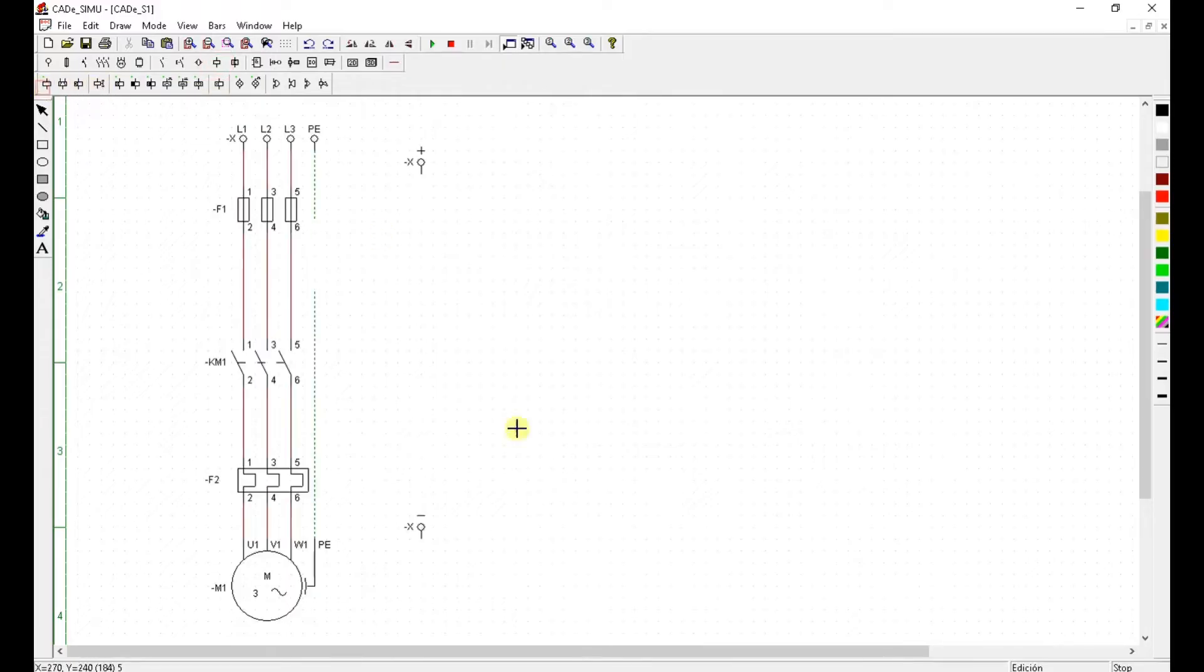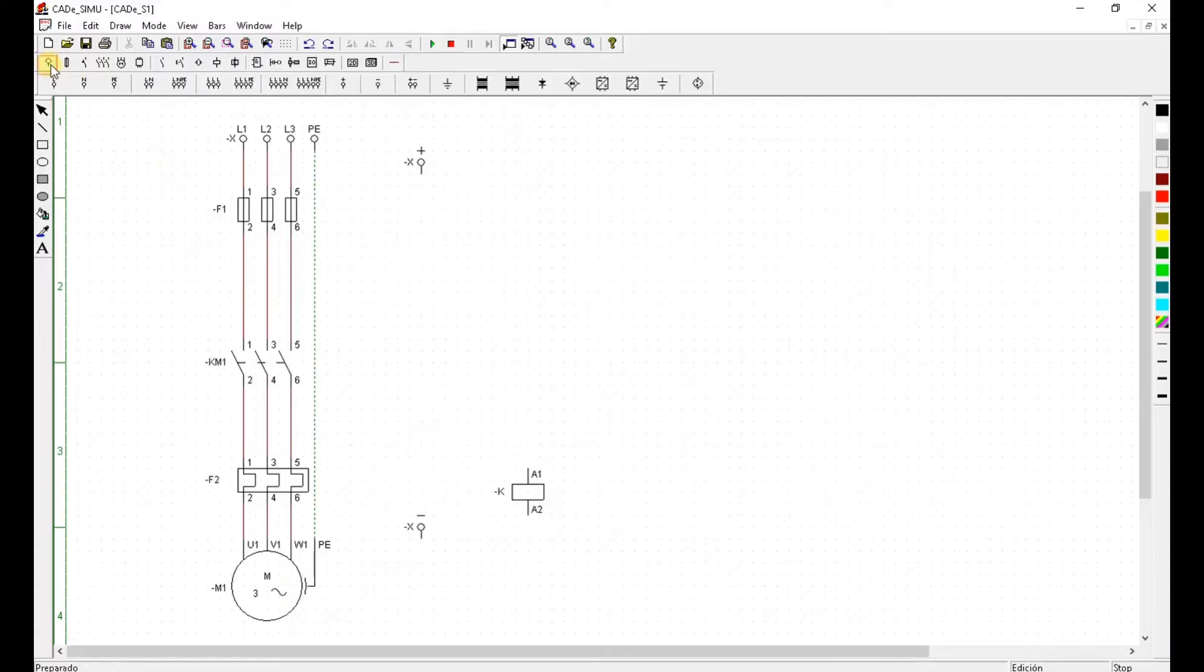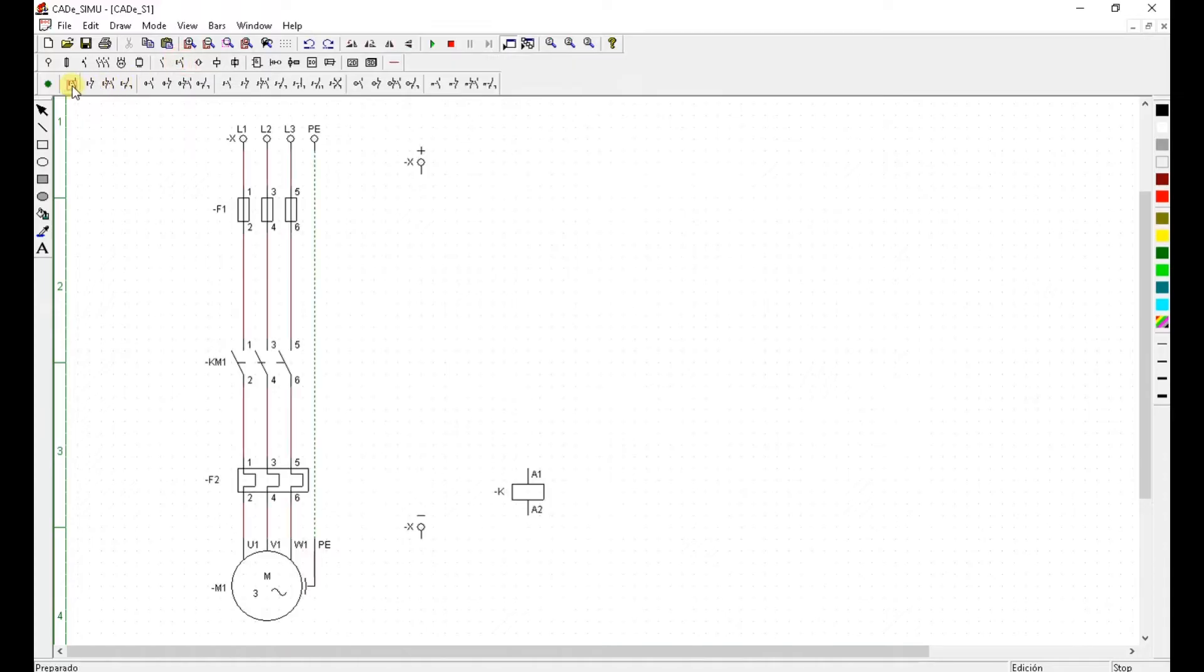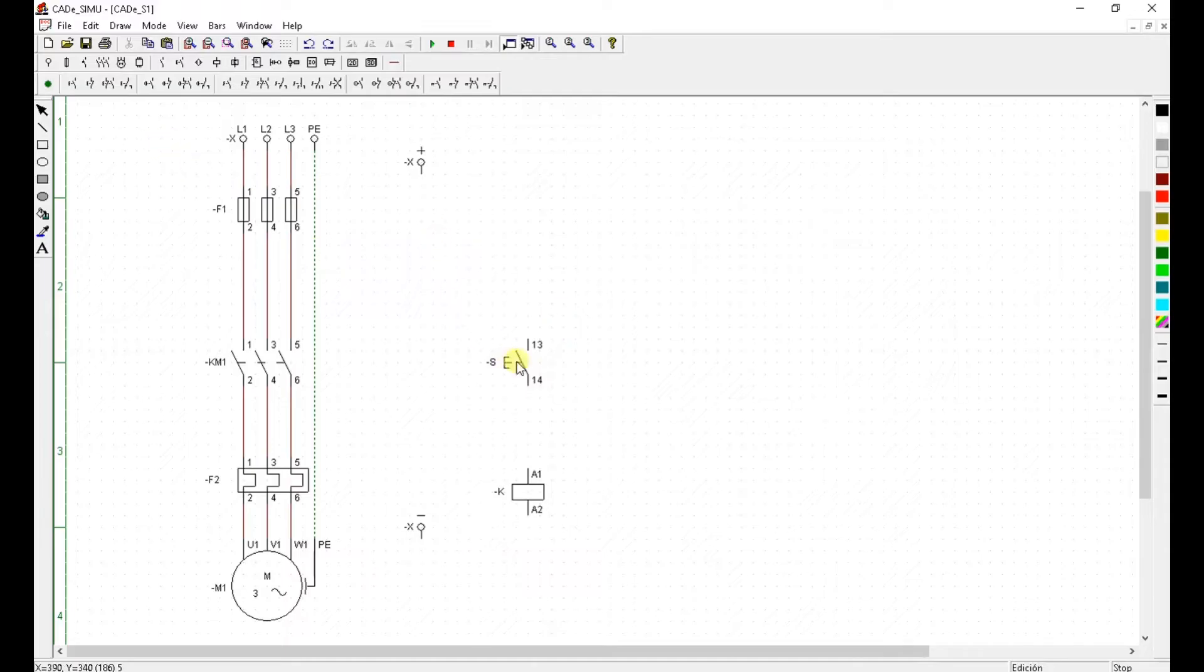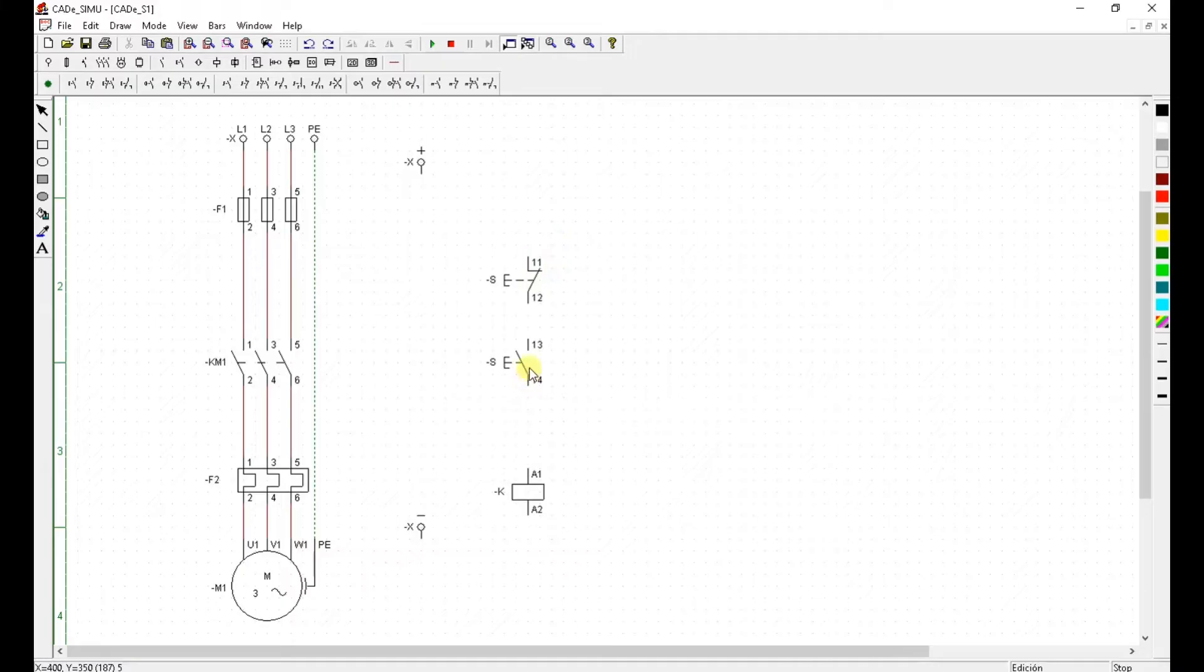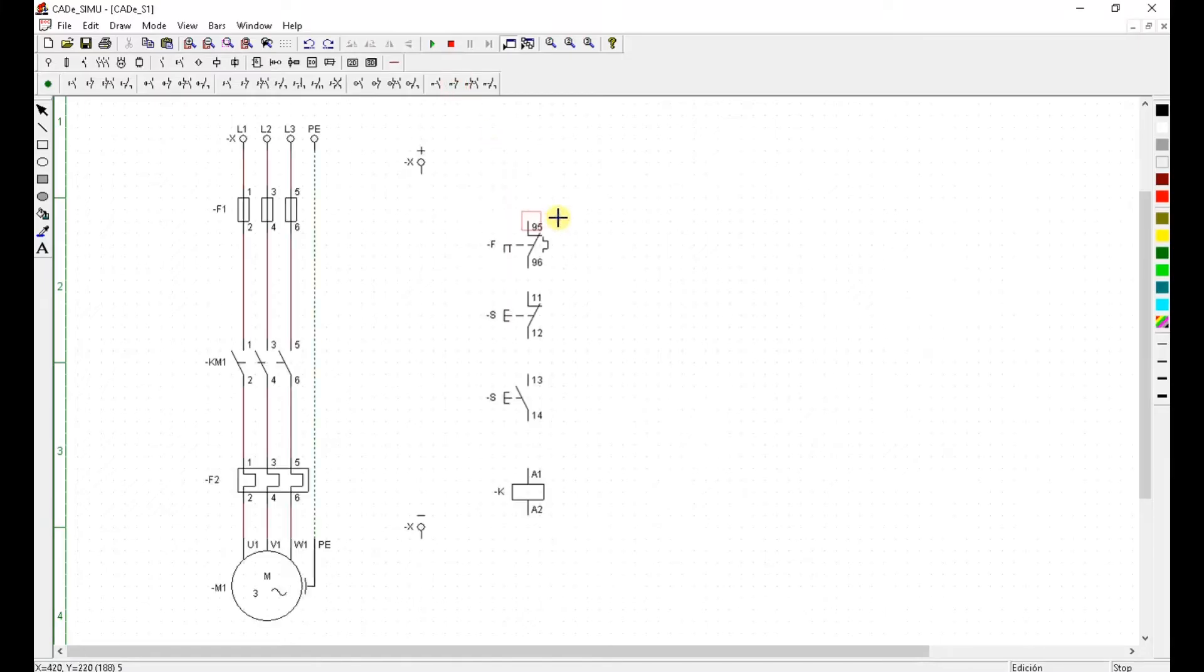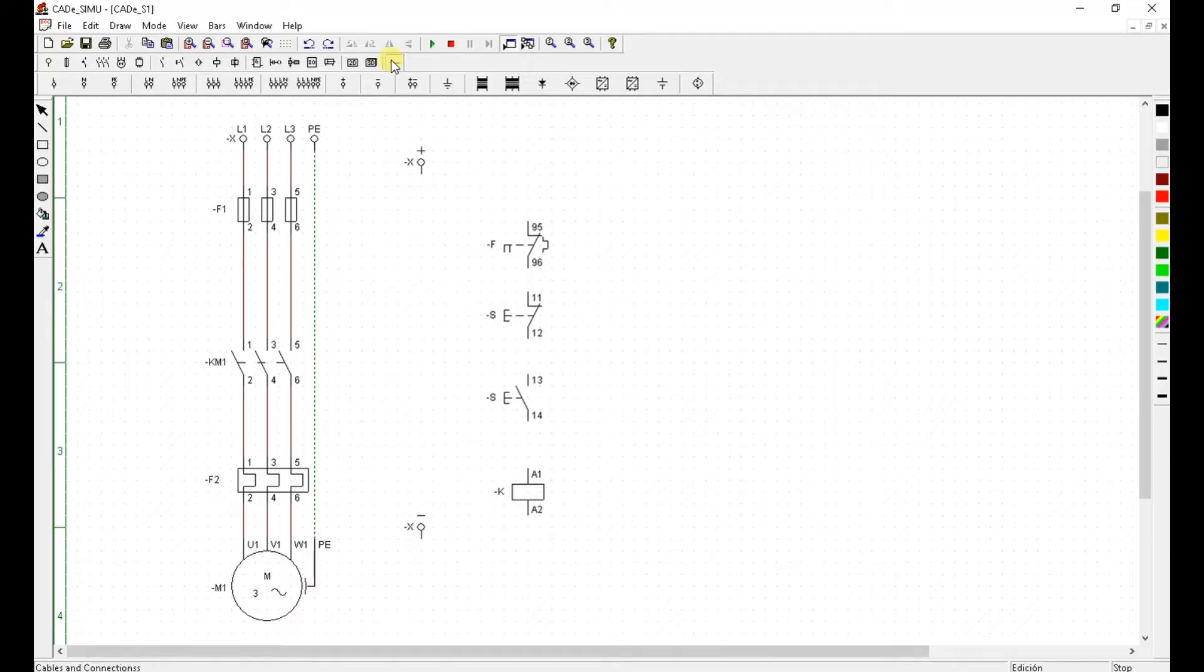Now elements I need is contactor coil. I need some sort of push buttons to start my motor, that's normally open push button. To stop my motor I'm going to use normally closed push button. And the last thing I need is auxiliary of this heat relay which is here normally close auxiliary heat relay.